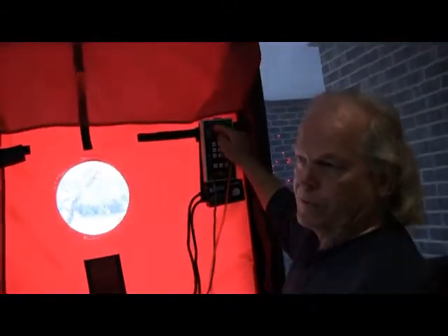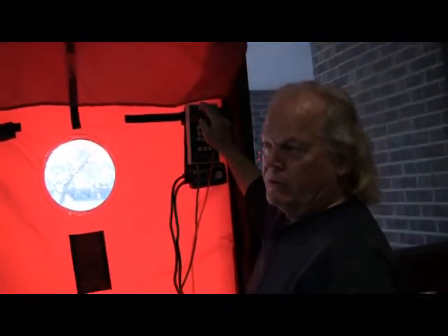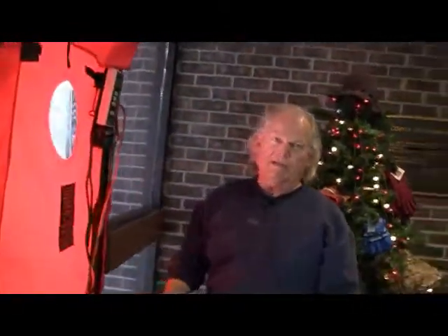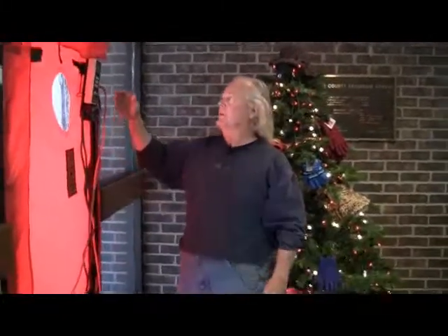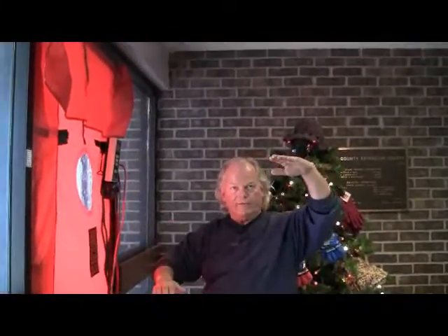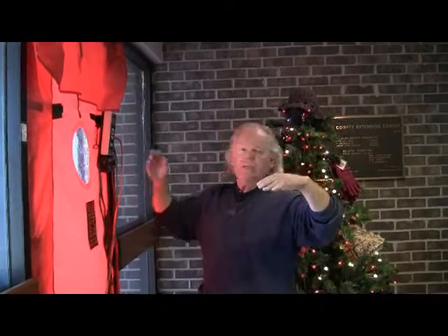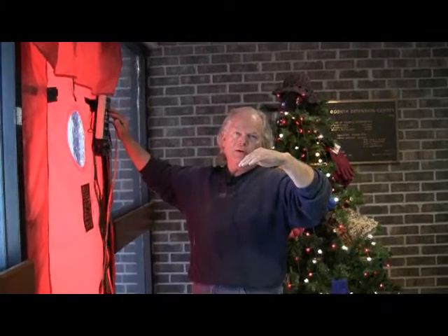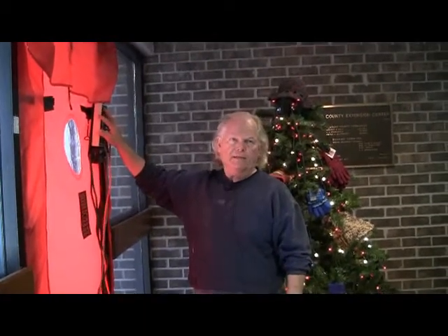As we took the reading on this building, we were able to get it up to about 25-30 pascals. So this building is so leaky that this fan doesn't have the capacity to move enough air to create a 50 pascal pressure differential between inside and out. So we use a mathematical formula to calculate what the leakage would be if we were able to move that much air. We've determined that this building has a leakage rate of about 0.81 air changes per hour. About 80% of the air is exchanged with outside air every hour in this building. That's a lot of air leakage. We think that there's a real opportunity to save money by doing some air sealing in this building.